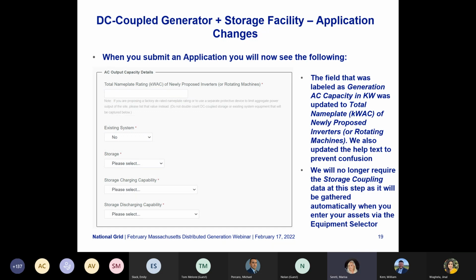Now you'll see the following when you submit an application: the field labeled generation AC capacity in kW was updated to total nameplate kWAC of newly proposed inverters or rotating machines. We also updated the help text to prevent confusion. We will no longer require storage coupling data at this step, since it will be gathered automatically when you enter your assets via the equipment selector. There's also a note stating: if you are proposing a factory derated nameplate rating, or using a separate protective device to limit aggregate power output of the site, list that value instead — and do not double count DC coupled storage or existing system equipment that will be captured below.